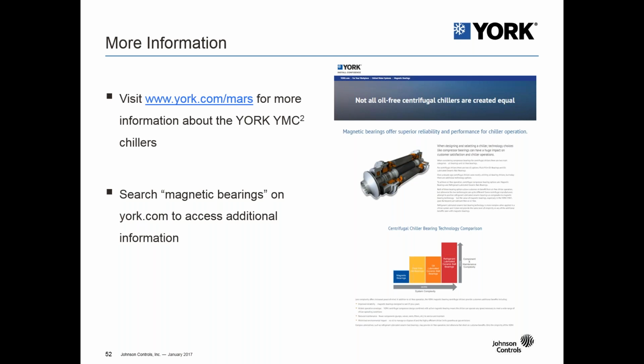Yeah, so when looking at the case study and what we went over earlier in the presentation, there is a premium for magnetic bearings. Just the inherent first costs of the system are higher because of the technology. But when comparing the total system costs of a chiller and a water side economizer, the first cost of the YMC² chiller is significantly less than it would be to buy a traditional chiller with a water side economizer. So the savings of eliminating that water side economizer is an immediate savings to most applications.